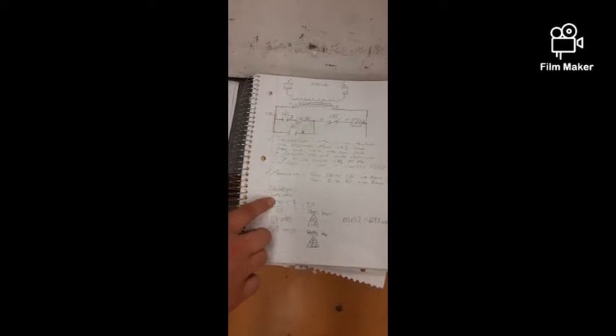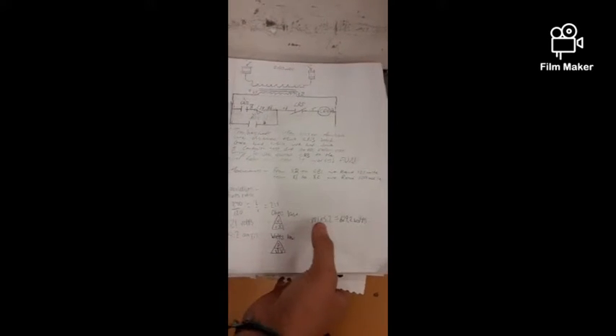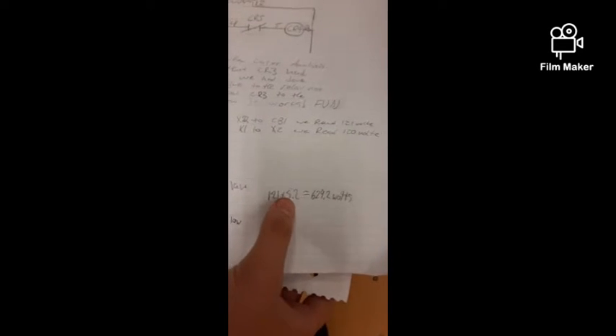And then for the calculations, we use the turns ratio. So 240 volts going in, 120 coming out, so it'd be 2:1 for the turns ratio. Then we used Watt's law. We measured 121 volts at 5.2 amps, so we multiplied the volts by the amps to get the total wattage.